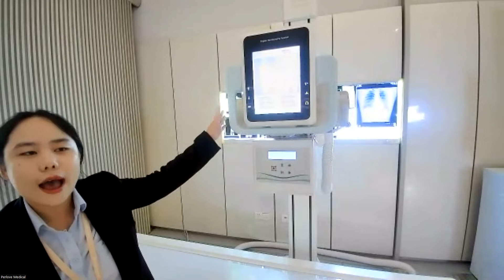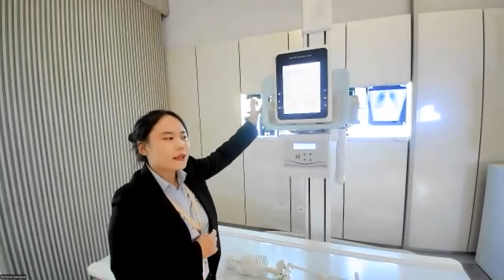Why? That is because the Canon Toshiba tube is very famous for its using experience. No problem for us to use this tube for more than 8 to 10 years. And for the revolutions per minute, we can be up to 10,000 revolutions per minute. So, according to the data, with this machine, in half a day, we can do more than 300 radiography checks. So every day, we can do around 600 images. It's very large in number, right?